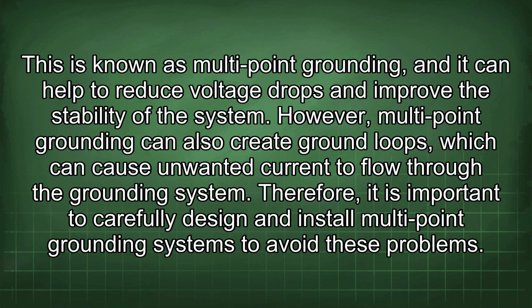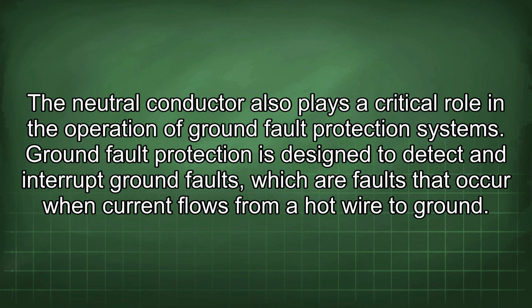However, multi-point grounding can also create ground loops, which can cause unwanted current to flow through the grounding system. Therefore, it is important to carefully design and install multi-point grounding systems to avoid these problems. The neutral conductor also plays a critical role in the operation of ground fault protection systems.